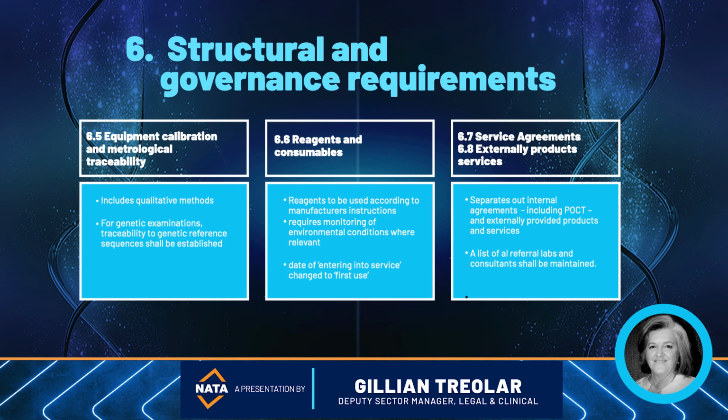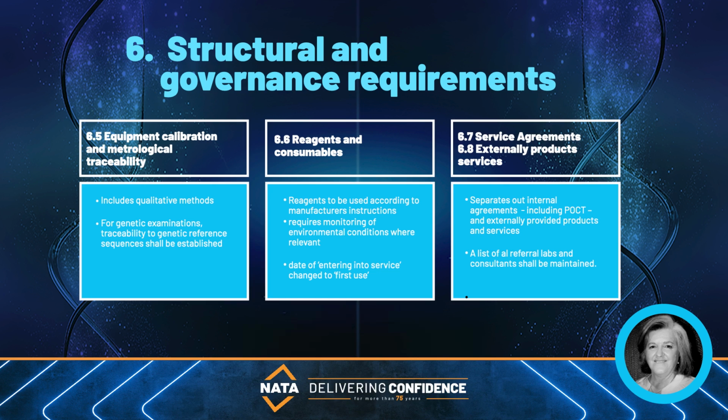Metrological traceability is required for both quantitative and qualitative methods. Labs shall have procedures for the calibration of equipment that affects exam results, including where correction factors are used, how these are recorded, and how to handle cases where calibration is out of control to minimise patient risk. Labs shall establish and maintain metrological traceability by means of a documented, unbroken chain of calibrations and ensure that results are traceable to the highest possible level of traceability.